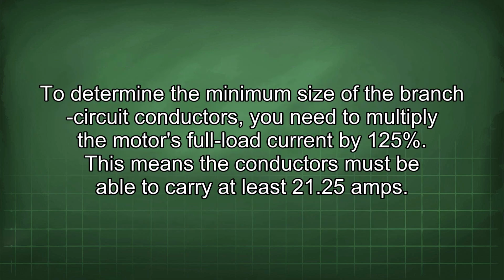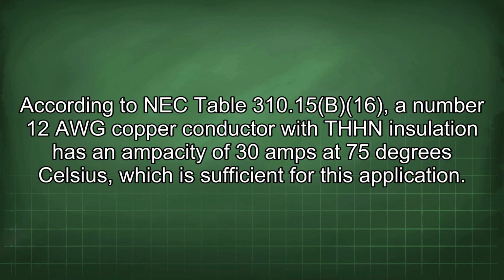430.248. To determine the minimum size of the branch circuit conductors, you need to multiply the motor's full load current by 125%. This means the conductors must be able to carry at least 21.25 amps. According to NEC table 310.15(B)(16), a number 12 AWG copper conductor with THHN insulation has an ampacity of 30 amps at 75 degrees Celsius, which is sufficient for this application.